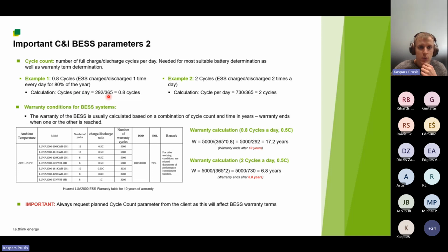So if we know that we will have these 292 days that we want this battery to be charged or discharged, then we just divide it by 365 and we will get this cycle count, which in this case is 0.8 cycles. And the second example is that we know that our battery will be discharged approximately 2 times each day. And this means that in total per year, there's going to be 730 charge-discharge cycles. And of course, if we divide by 365, we get 2 cycles per day.